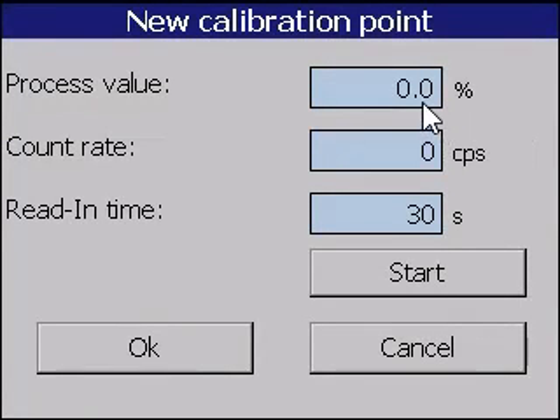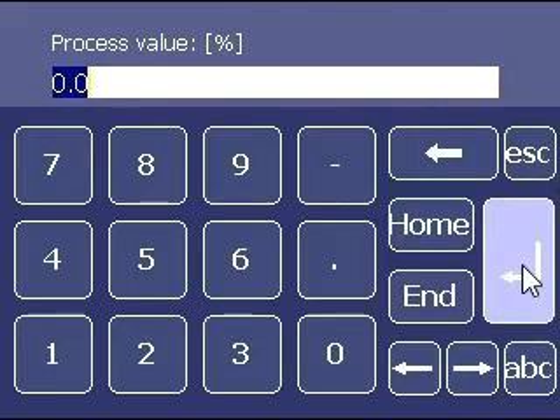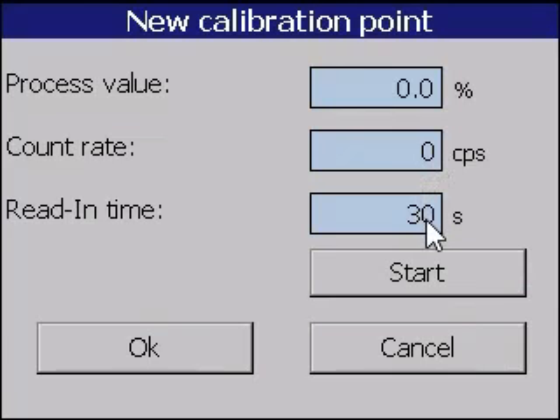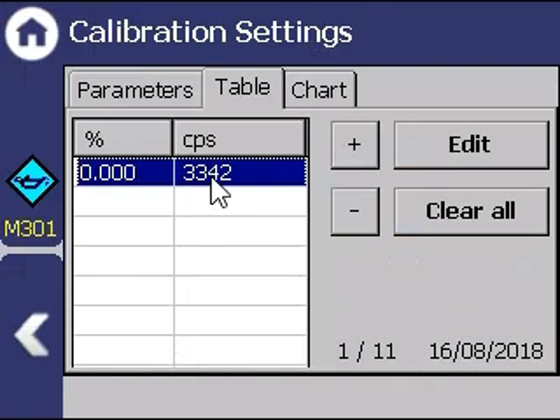Select what you want the process value to be for this point. We will say this is 0%. As mentioned, we have ensured that our vessel is empty and the source is open. Press the start. We have a 30-second read-in time selected. A longer read-in can be beneficial for better averaging, allowing the counts to further stabilize. When the time has elapsed, press OK. You will now see the new point populated in the table.